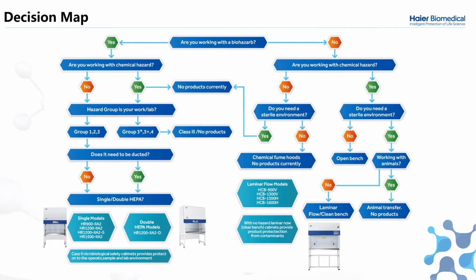Things such as what hazard group are they working with? Is it a chemical hazard? If so, we don't currently supply fume hoods. However, if it's a non-chemical hazard, which hazard group are they working with? Is it 1, 2, 3? In which case, biological class 2. Is it 3 plus or 4? In which case, we don't currently offer those products. However, a class 3 would be appropriate here. In the case of requiring a sterile environment with no biological or chemical hazards, we point them towards the Laminar Flow cabinet. This decision map should be part of the sales process when helping you make recommendations.